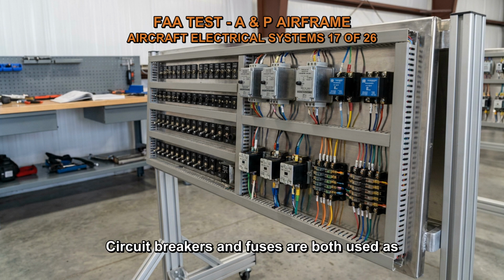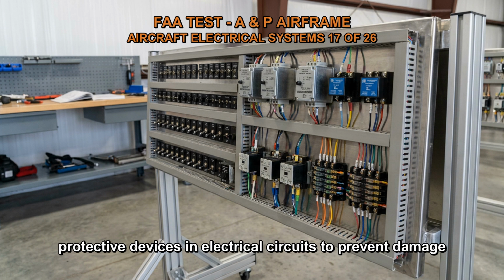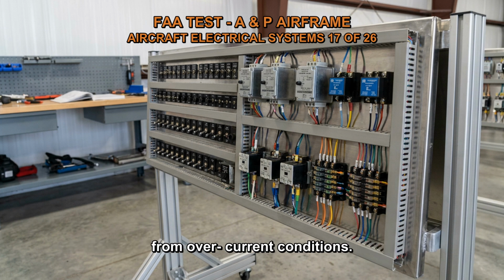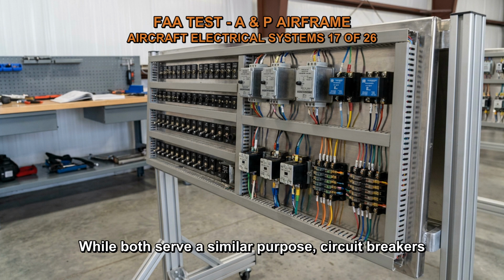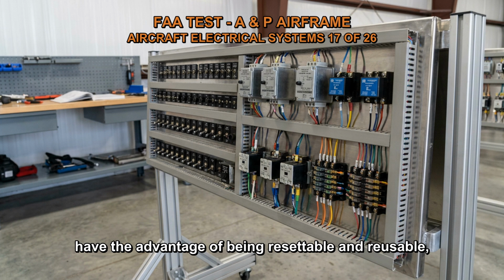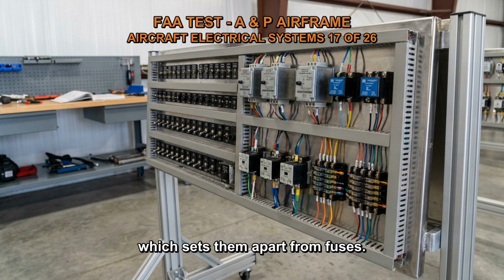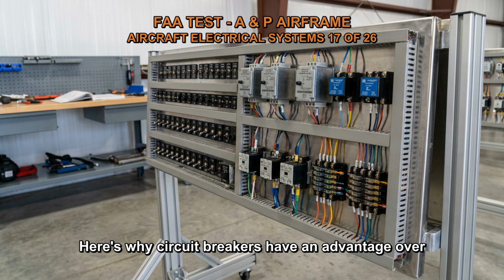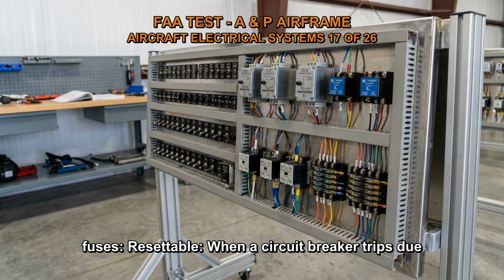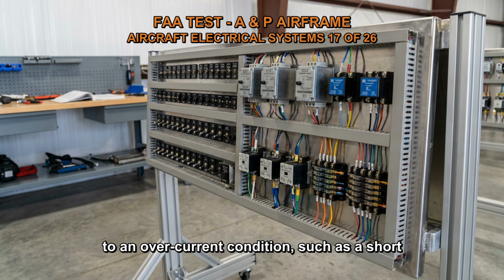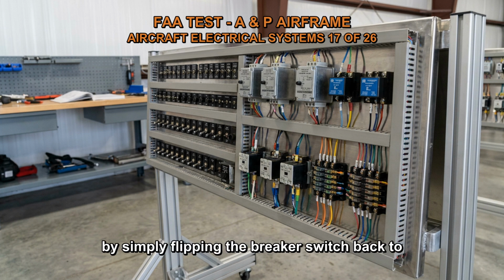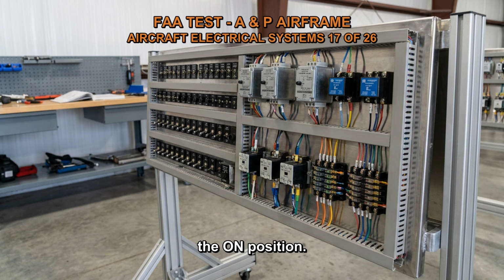Circuit breakers and fuses are both used as protective devices in electrical circuits to prevent damage from overcurrent conditions. While both serve a similar purpose, circuit breakers have the advantage of being resettable and reusable, which sets them apart from fuses. Here's why circuit breakers have an advantage over fuses. Resettable. When a circuit breaker trips due to an overcurrent condition, such as a short circuit or overload, it can be easily reset by simply flipping the breaker switch back to the on position.